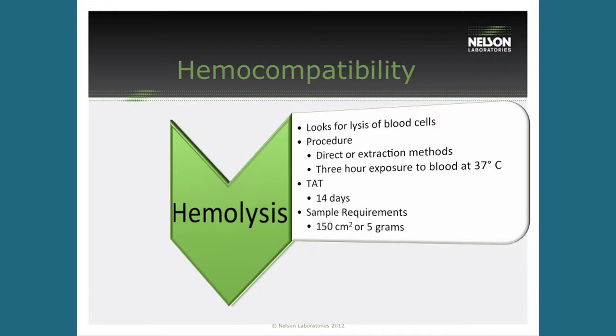I want to hit a couple of tests very quickly so you have the information. With hemocompatibility, the first one is hemolysis testing. Hemolysis is kind of a cytotoxicity test but solely looks at cytotoxicity for red blood cells. We take your device and put it in both direct contact and we extract it and put that extract in contact with blood. The basis behind this is we want to see how your device interacts with blood — we evaluate both mechanical damage of the hemolysis cells against your device and long-term exposure by extracting at 50°C to see what might come off.